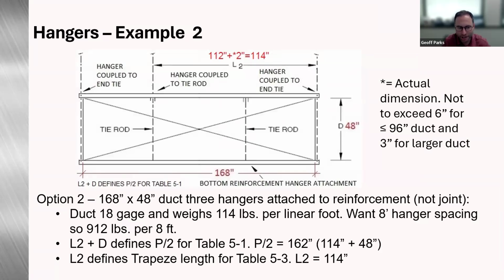Looking at our second option here, so this was, instead of using the L1 dimension, we're now going to use our L2 dimension. So again, same duct size, 168 by 48, 3 hangers, and instead of going to the midpoint of this ductwork, now we're going to tie into one of the tie rods. So again, using all the same, 18 gauge, our duct's 912 pounds per 8 feet.